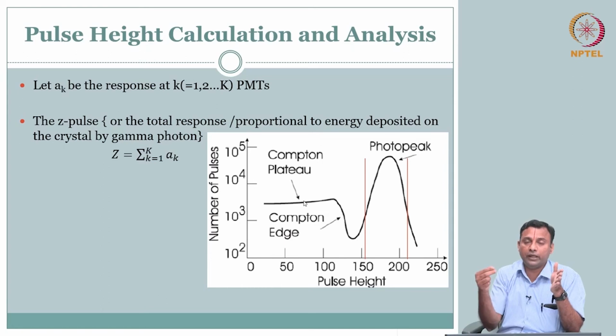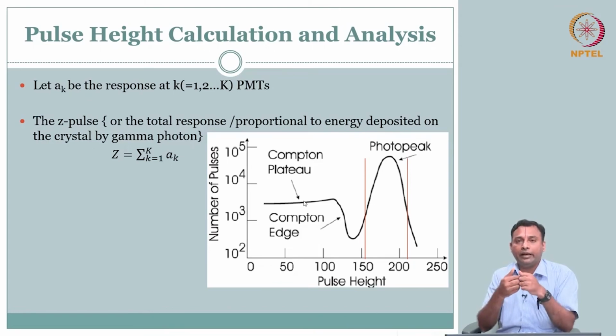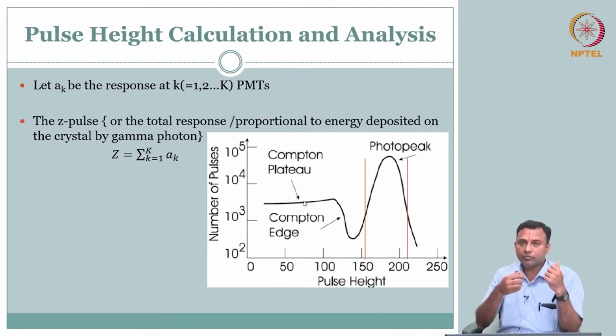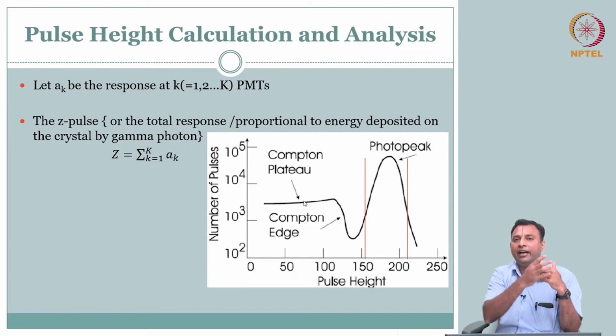You have the collimator and then this crystal, and not all interactions in the crystal give light energy. Maybe you get Compton interaction, not just photoelectric. The Compton scattered photon will go to a different location and maybe generate the light photons there.